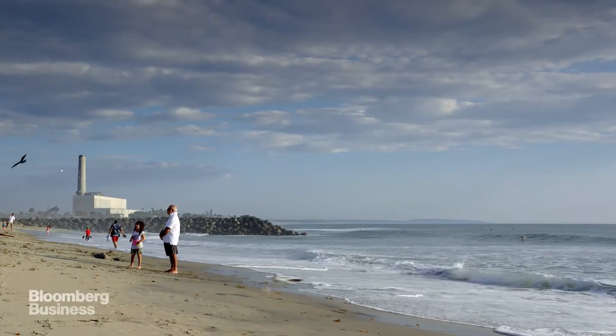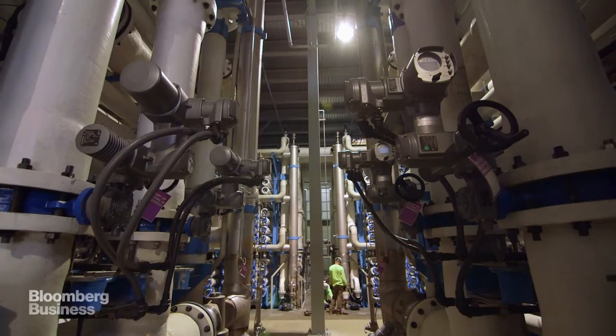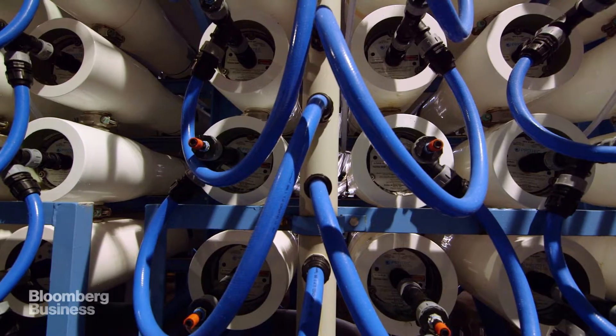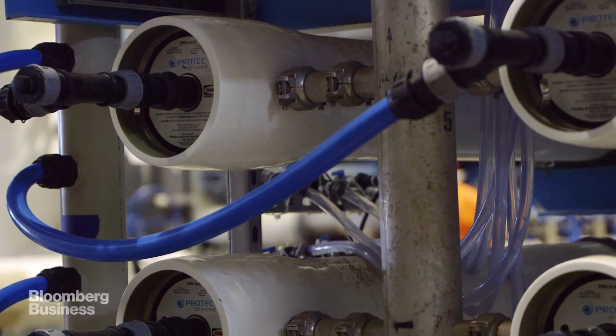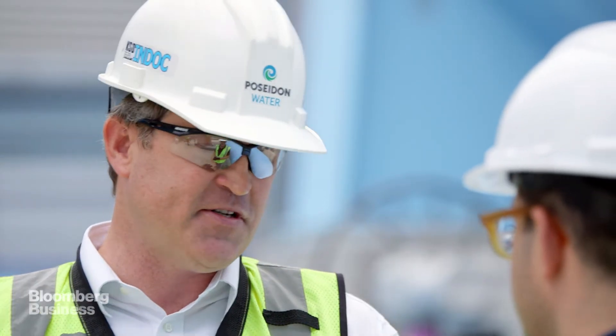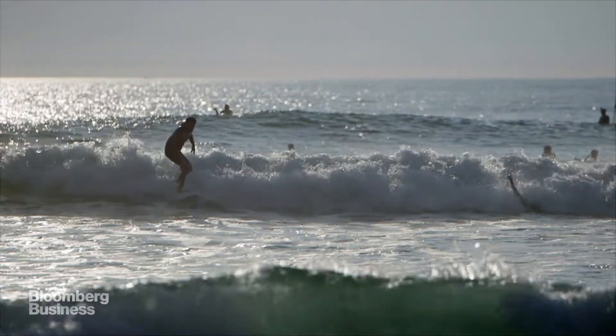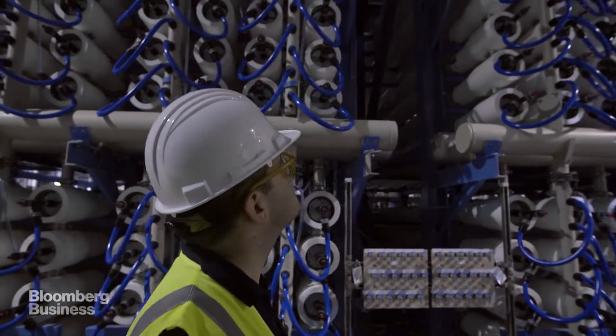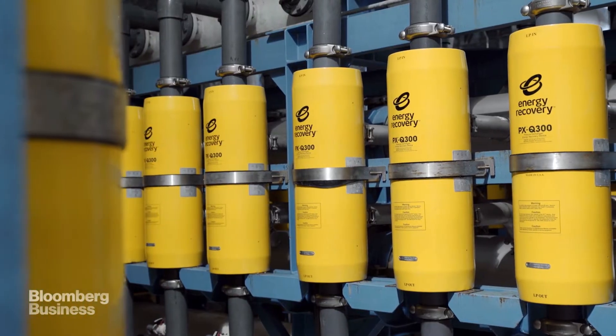This is also where the whole idea of converting seawater to drinking water starts to run into trouble. The reverse osmosis process requires a significant amount of pressure, and that pressure requires energy. We consume between 33 and 38 megawatts of power — we're the single largest power user in San Diego County. All that power costs money, and this is why seawater desalination has never really worked in the U.S. — we've always had cheaper water sources available. So the developers of the Carlsbad plant have spent about a billion dollars trying to make it as efficient as it possibly can be.